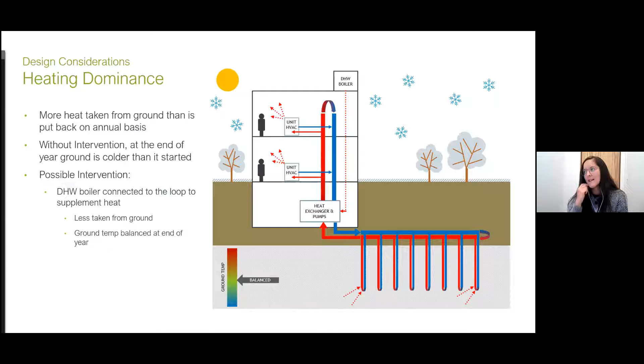What's great about geothermal is that, yes, the loops go through the ground and that's where the heat transfer takes place, but ultimately the loop doesn't care where the heat comes from. So if you need to supplement with heat from another source like a boiler, or if you've got a really creative design team and can figure out something like a reverse snow melt, where you're absorbing heat in the summer to put back into the system, you can get really creative. It's really just about getting heat into the loop, and there are ways to do that depending on how creative your team wants to get.